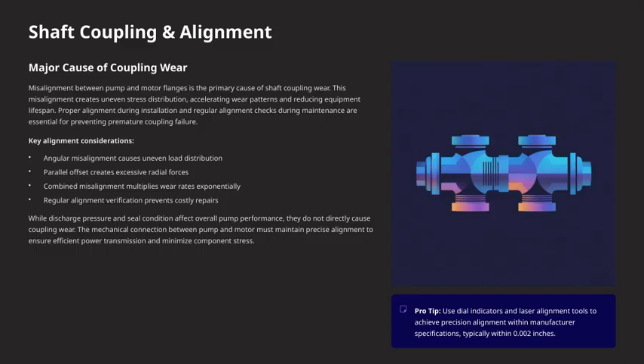It's worth noting that while discharge pressure and seal condition do impact overall pump performance, they don't directly cause coupling wear. The mechanical connection between the pump and motor must stay precisely aligned to ensure efficient power transfer and reduce stress on components. Here's a pro tip. Use tools like dial indicators and laser alignment devices. These help you achieve the kind of precision alignment that manufacturers specify, typically within 0.002 inches. Staying on top of alignment is a simple yet effective way to extend your equipment's life and avoid unnecessary downtime.